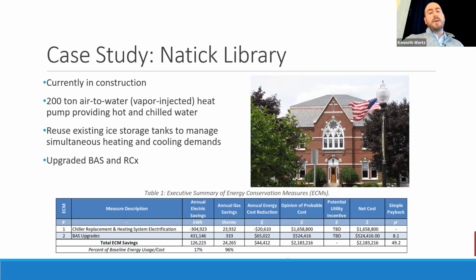efficient option. But they were able to make the overall project work because they did a lot of energy conservation work at the same time. So they upgraded their control system, they recommissioned and replaced a bunch of failing equipment, they added VFDs, they added occupancy sensors, things like that, that can help minimize how much energy the rest of the system's using, even if the heat pump is using a lot more electricity than they were planning before.